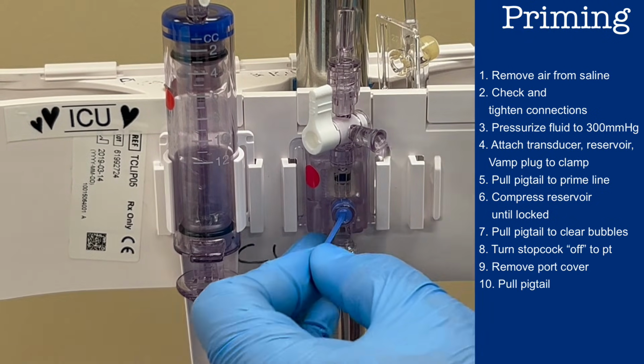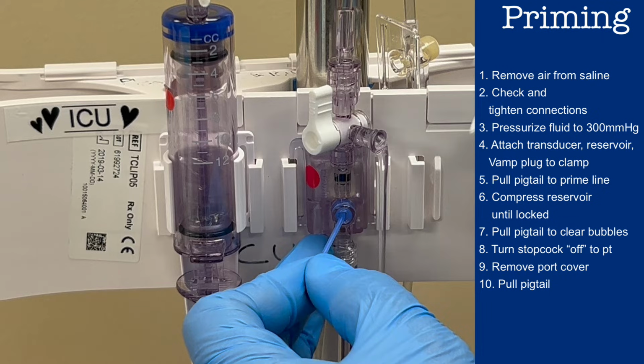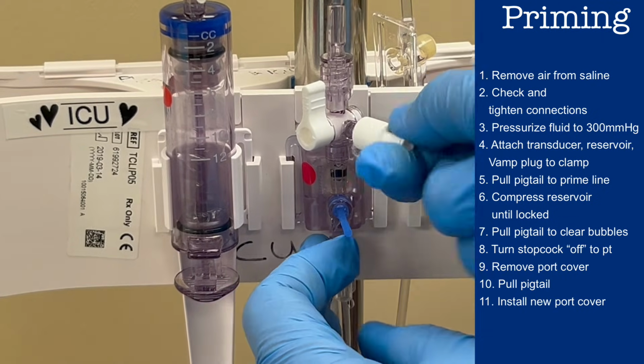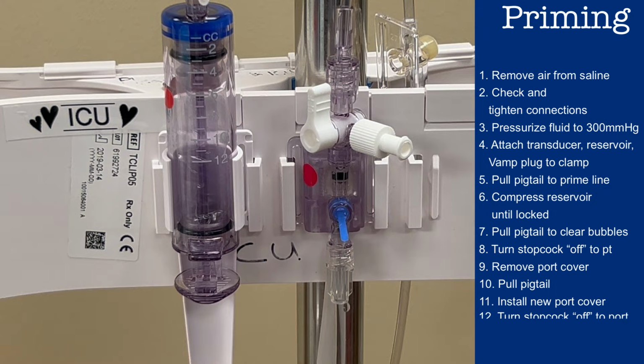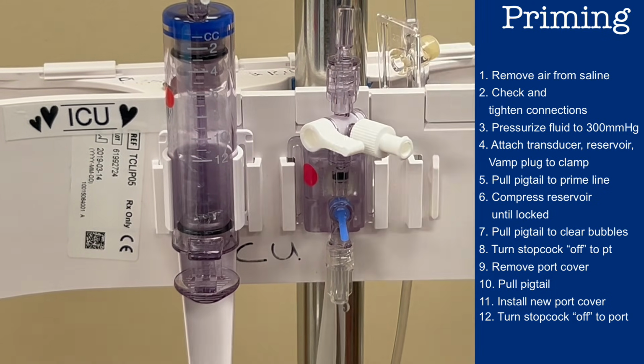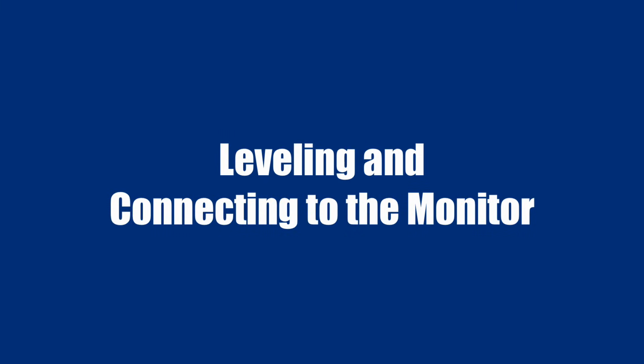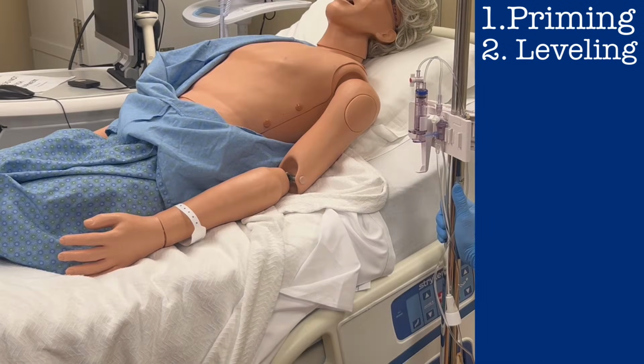Pull the pigtail, and you should see saline start to exit that port. Let go of the pigtail and connect the new white cap. Then turn the stopcock to the right so that it is off to the outside port you just drained. Your tubing is now primed, but now you should take the time to level the transducer to the patient and connect the monitor. First, you need to level the transducer with the patient's phlebostatic axis.